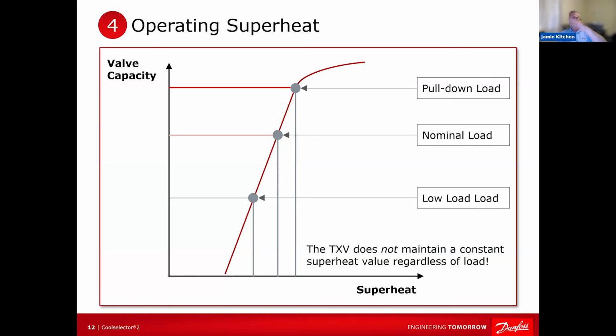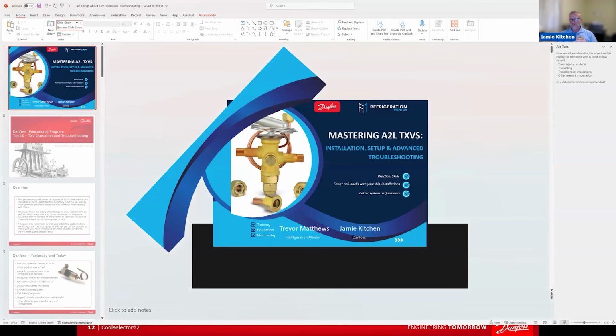But essentially, when you think about it, as the load on the evaporator increases, your superheat increases, and the sensing bulb increases in temperature. That's going to drive the pressure on the diaphragm down. And the reason this extra pressure is required is because when you compress a spring, it pushes back. So the harder you push it, the harder it's going to push back until it's fully compressed. And a lot of times what you'll see, and again, you can flatten this out, there's all kinds of things you can do.